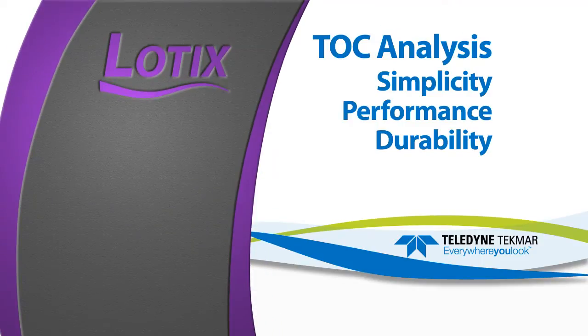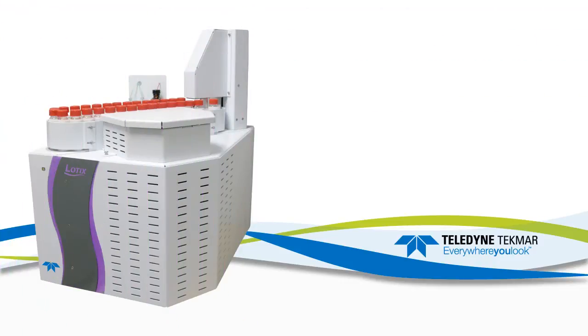The Lotix TOC Combustion Analyzer is designed to accurately measure carbon content in aqueous matrices down to the parts per billion level. It uses proven high temperature combustion, oxidation of carbon material into carbon dioxide, and detection using a new NDIR detector.